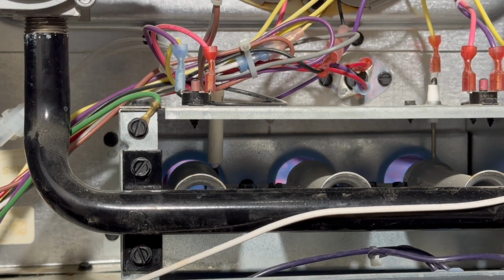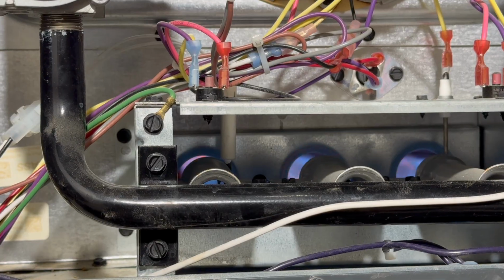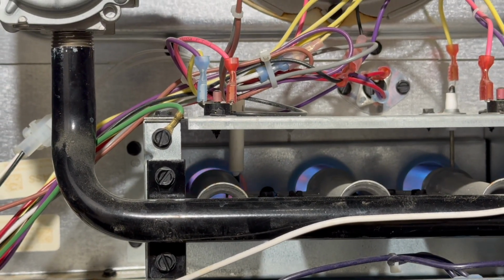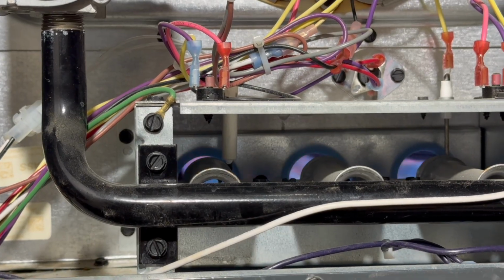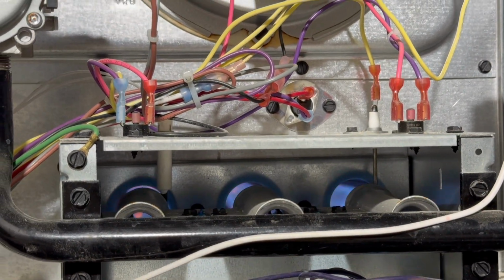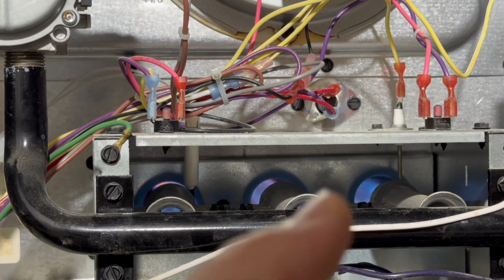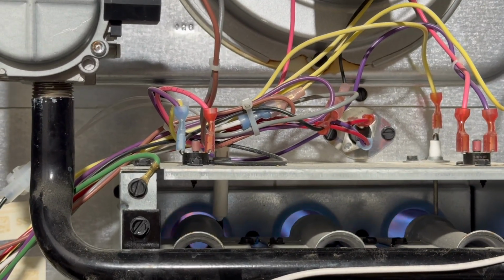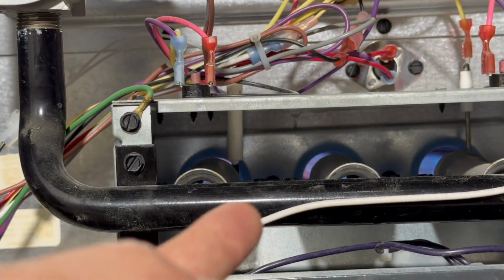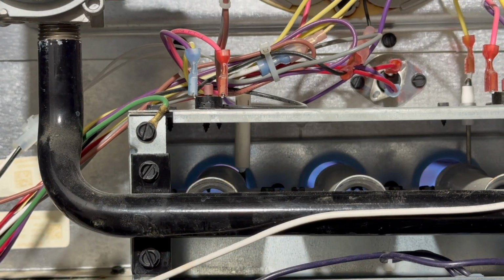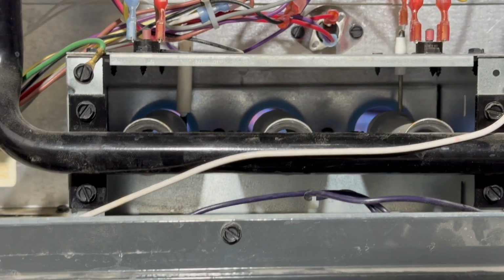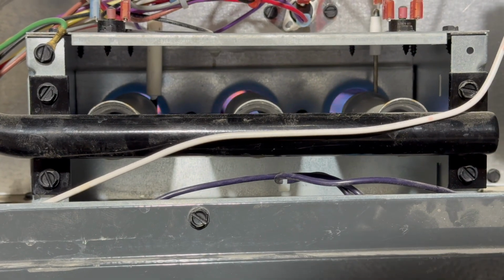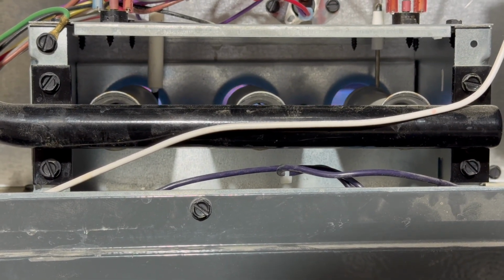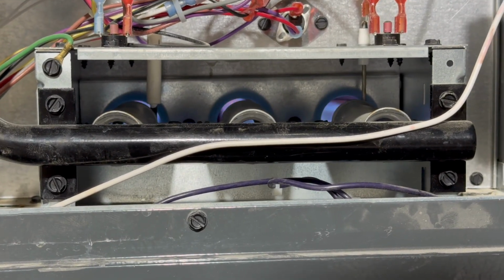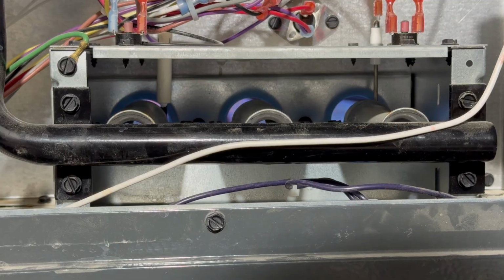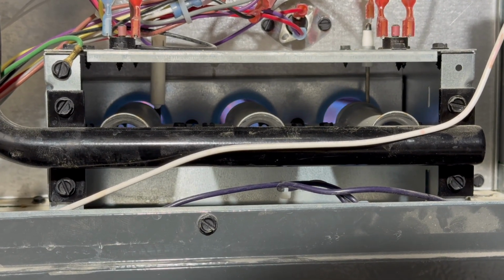But most of the time, from what I have experienced over the past several years, the flame would not stay over there. That means the flame sensor is bad. So if you're going to change the flame sensor, just pre-order it. This is just a cheap thing. Same thing with the igniter. You can order online, or you can get it from Lowe's or Home Depot. They're widely available, I would say. So it's better to have those if you're troubleshooting on your own, and you can try both. If you want to replace them, you can, and I'm hopeful that it will work out for you guys.